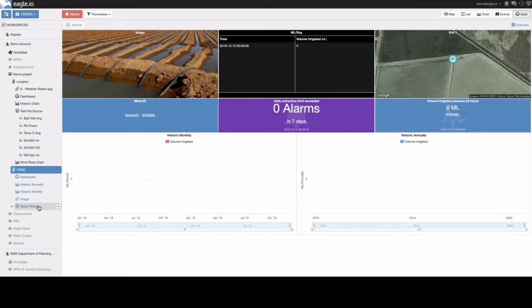It's in direct relationship with it, meaning that if I deployed 100 sites with all the configuration pre-done, I could make a change in the template and it will reflect across all instances that have been created from it, from bringing in a new chart into the dashboard to your 100 sites, or maybe removing a chart or something like that. This saves you a lot of time and ensures consistent configuration when doing deployment of multiple sites that have a very similar configuration.